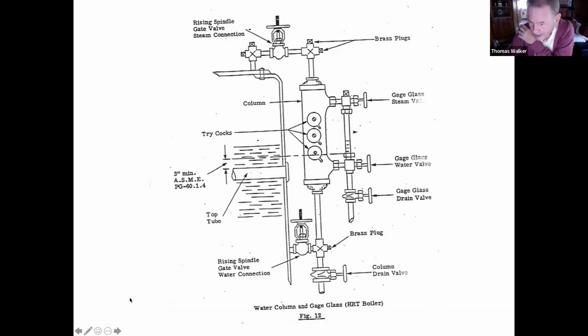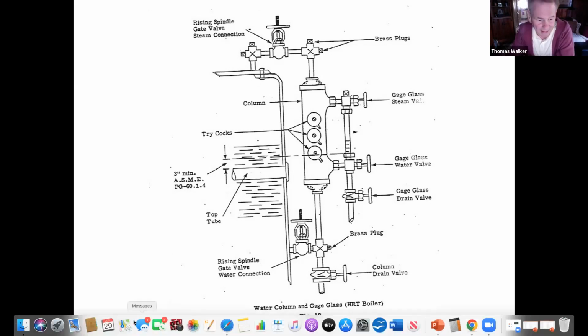How many low water cutouts are required on a boiler? 2 is the correct answer. What's the difference between the 2 low water cutouts? The second one requires a manual reset. It will not reset automatically once the water level's restored. Somebody physically has to manually reset it. All right, good.